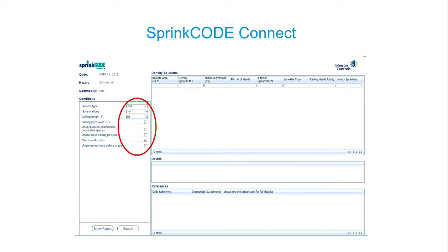You pick a code and a hazard. Because I picked NFPA 13 2019, that's the list of hazards within that code. For every hazard, you have a list of commodities. I've got a light hazard commercial commodity for this school example, and I created this new area. You click the search code button, and then there's a series of options to specify: is it a wet or dry system, are there hose stations, what's the ceiling height — I put in 10 feet — does the ceiling pitch over 2 and 12, et cetera.